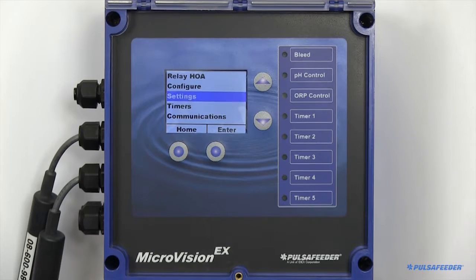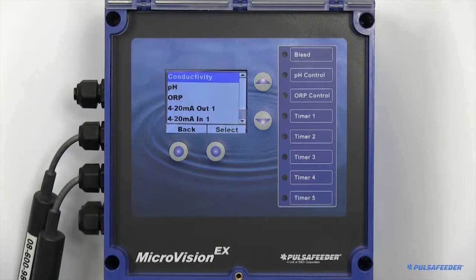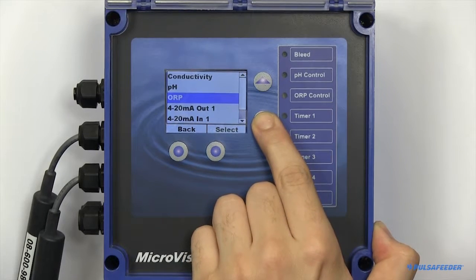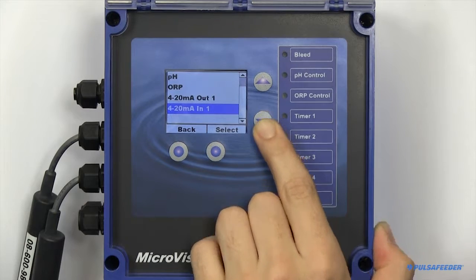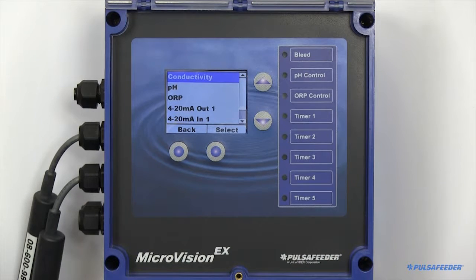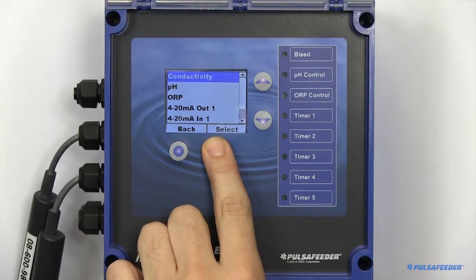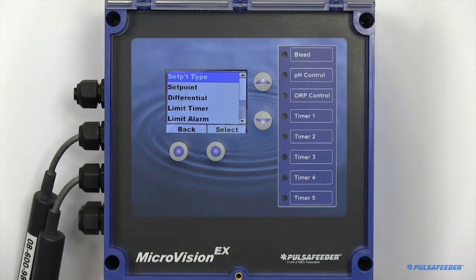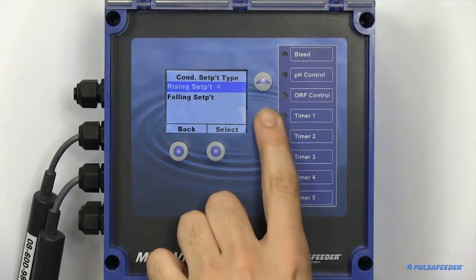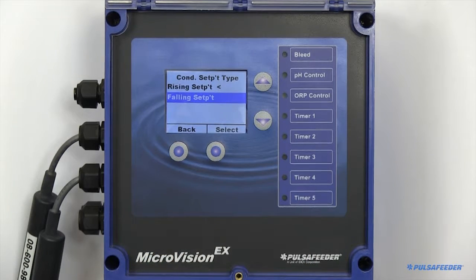The settings page is where you'll configure your probes, conductivity, pH, ORP, and any of your 4 to 20 peripherals. All probe types are configured the same way. This is an example of how to set up your conductivity probe. The pH and ORP probe will be done identically. To set up your conductivity probe, you need to choose your set point type. You can choose between rising or falling. Rising type means that the output activates when the input goes above the set point. Falling type activates the output when the value goes below the set point.